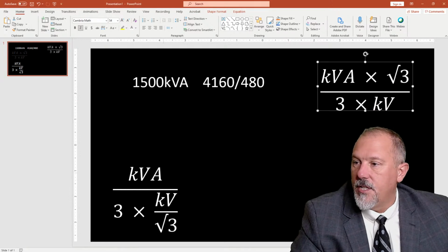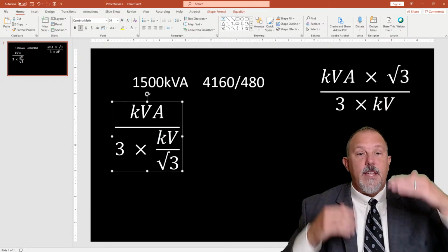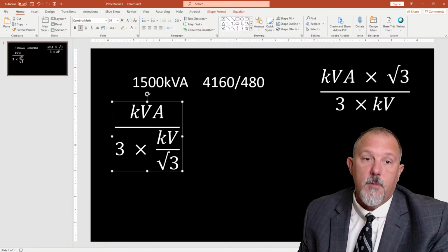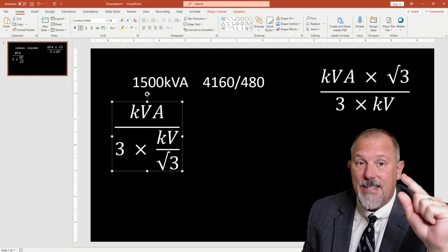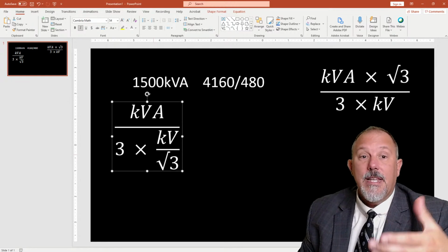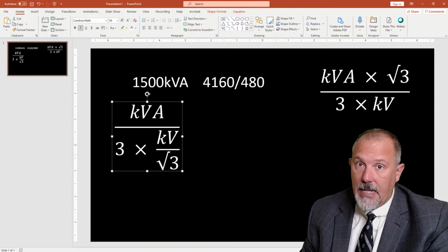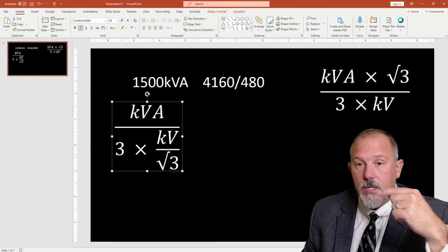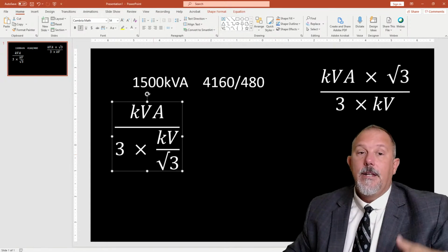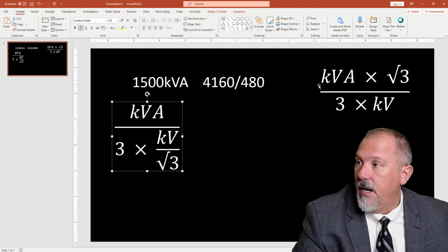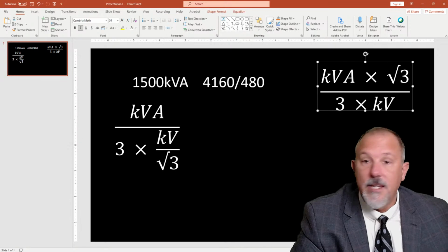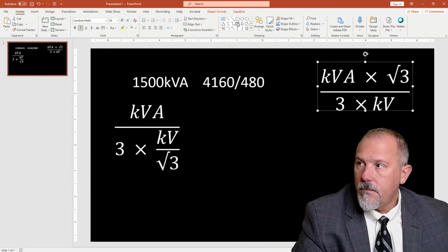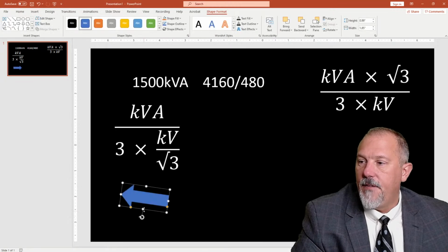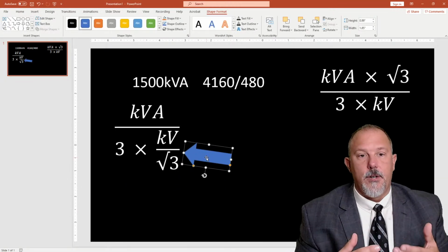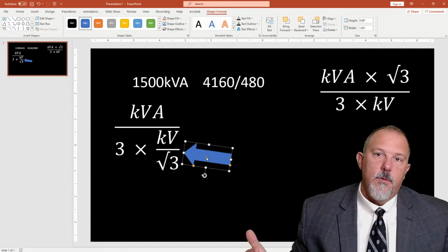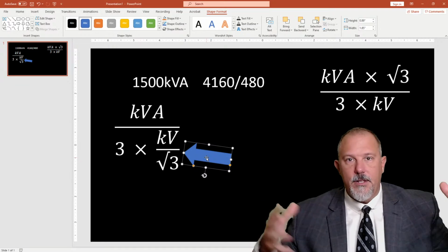So I've got a couple different equations that I can use. This is the long way. I have kVA divided by 3 because if it's a 3-phase transformer, I've got to divide my kVA to get it to a single phase kVA. And then I divide that by kV, which if it's a 3-phase kV, I have to divide by the square root of 3. So if I take that square root of 3, which is in the denominator, and put it in the numerator, now I am into this equation up here, right? So that's the basic equation. And this is what I'm talking about when I say it's that little math that I do here, which gives me a decimal. And if I round that and include it, then it just rounds things out.